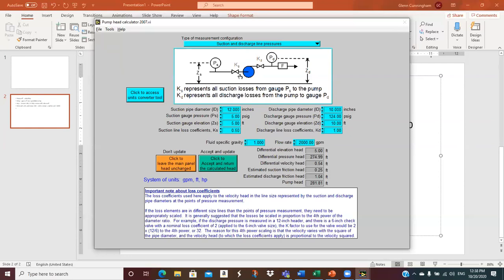Differential pressure head, well, gosh, what is it? For standard water, 1 PSI is 2.31 feet, roughly. So if I take this delta P, which is 119, times 2.31, it's 274.9. 274.99. So I'm off a tenth. So Don's got some extra digits in there. That's just doing the numbers for you.